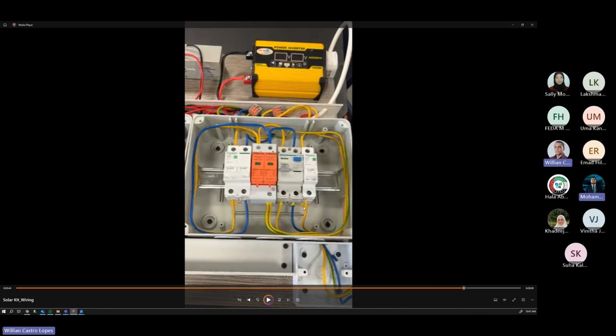Yes. For example, if you check the wire at the top here for the power inverter, you can see it's red and black, and there's a lot of red and black for the battery too. Should these all be brown and blue? No - this is DC, so it should be DC black and red. Yes, DC connection is black and red. Anyway, in case they don't deliver the brown one, I can use yellow - I will inform the student, but the point is they will get 5 different colors: black and red for DC circuit, blue, green, and a third color for AC circuit.